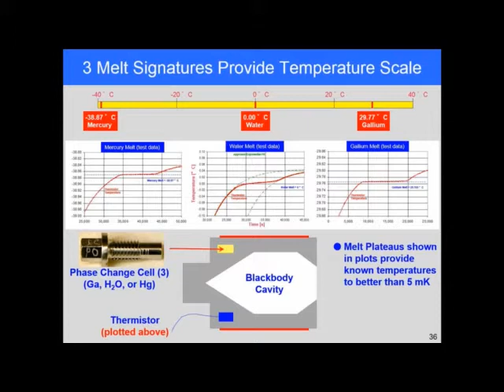If you want to be convinced that you're on this characteristic curve at any time, have at it. You can always go back and do it. And then, as I said, we're establishing a scale over a temperature range. So we have mercury at -39, water at 0, and gallium at 29. We go through the same process, and the melt plateaus, we can establish the melt temperature to within 5 millikelvin, 3 sigma.